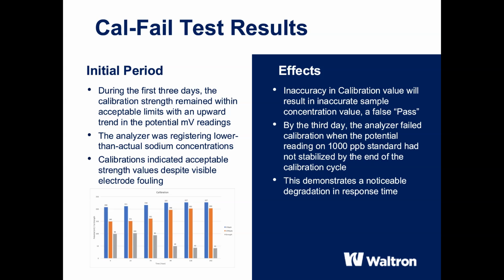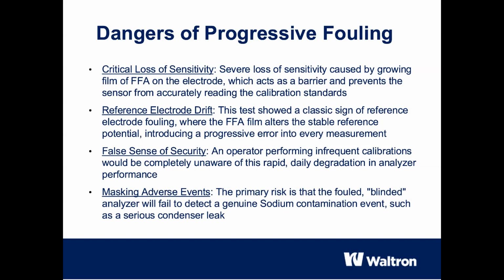The final failure occurred on the 3rd day. The analyzer was unable to complete the calibration because the reading for the 1000 ppb standard no longer stabilized within the specified time window due to the heavy contamination. This again demonstrates the noticeable deterioration in response time. Let's summarize the results and consider the real hazards to proper plant operation.